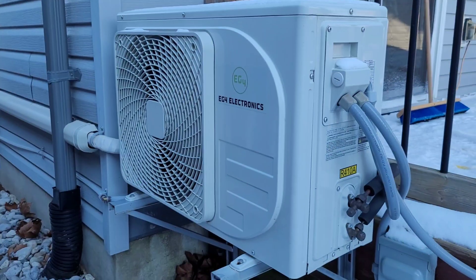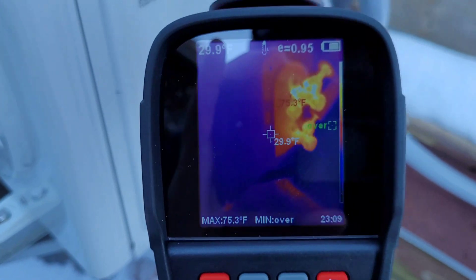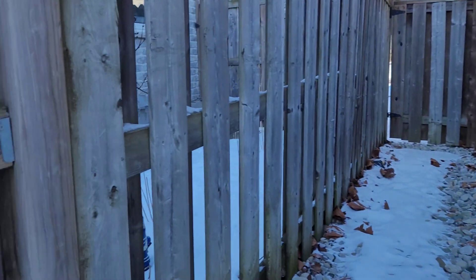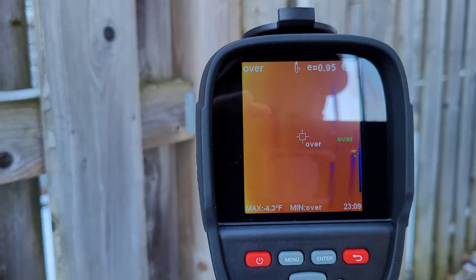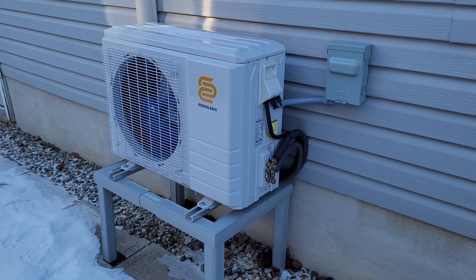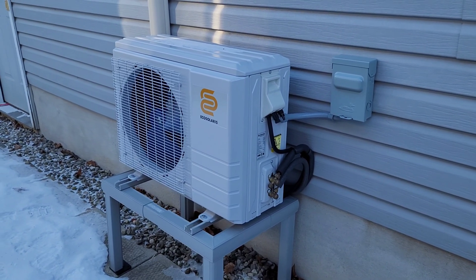Here's the outdoor unit — there's a good puddle of frozen water underneath it from defrost cycles. On the service valves we're sitting at about 75 degrees, which is about as good as we can ask for on a day like today. Over on the fence we're sitting at what appears to be beyond range — it showed minus 7 Fahrenheit a minute ago. The Eco Solaris heat pump is doing pretty well despite being too close to the wall. I'll need to move that out in the future and give it a bit more room to breathe.